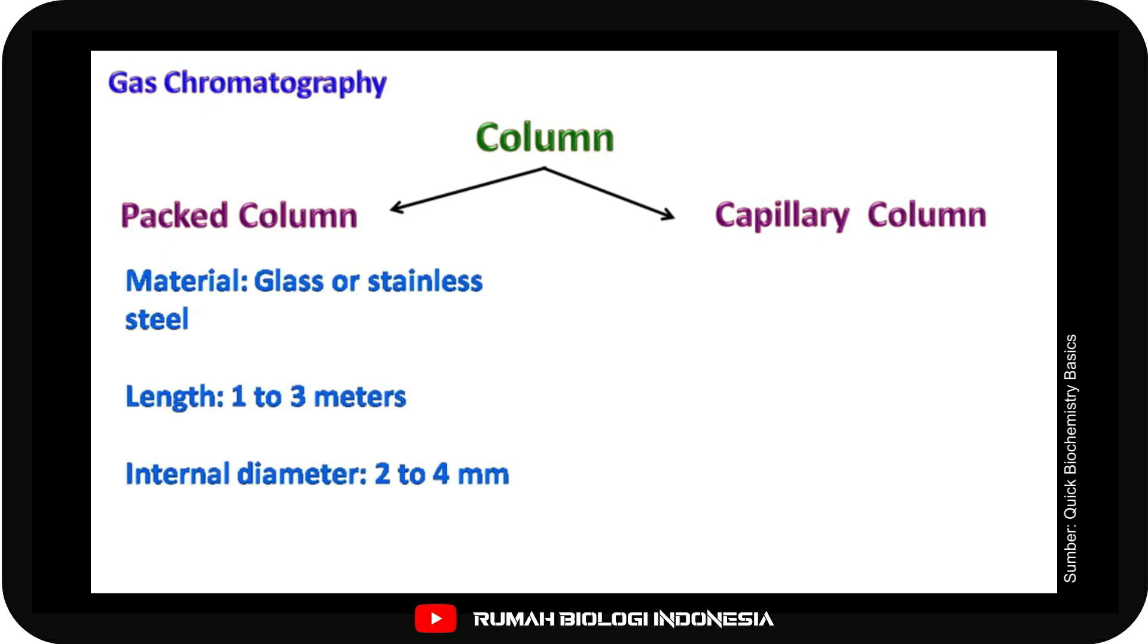Packed column can be made up of glass or stainless steel. The length of this column can vary from 1 to 3 meters and has an internal diameter of 2 to 4 millimeters.